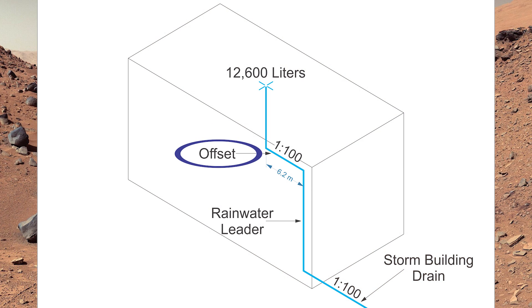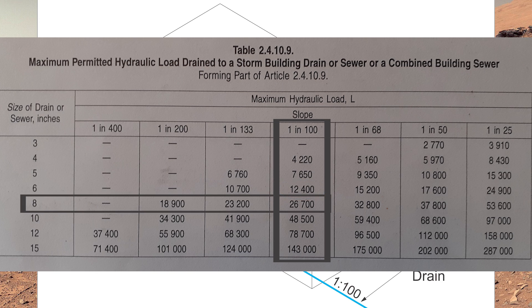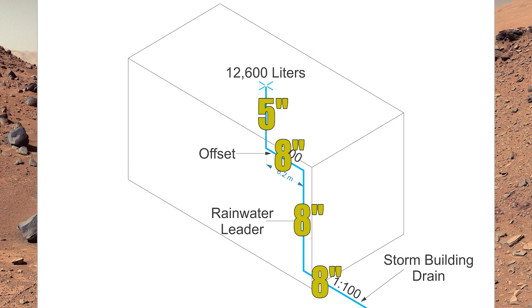But as soon as we get to that offset, we need to change to table 24109. Now we're at 1 in 100. I have 12,400 at six inch — but I've got 12,600, so that's not quite enough. Going down to the next value in the 1 in 100 slope column, I'm down to eight inches now. See how that changed everything just by changing the slope? Everything following that offset will be eight inches, including the next section of rainwater leader — you would never want to reduce that size, as it goes directly against plumbing code.